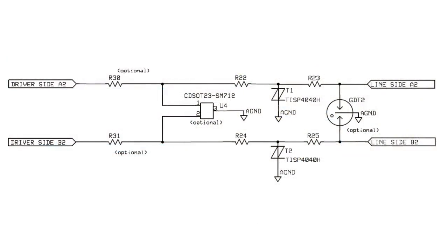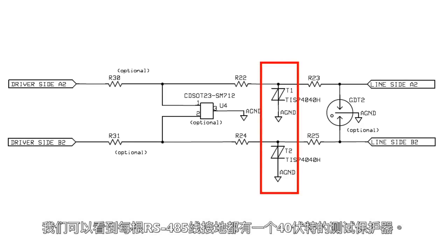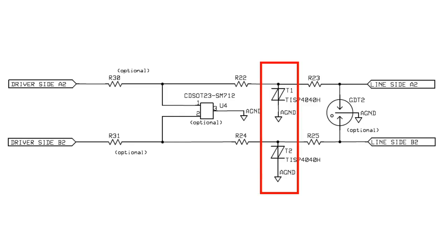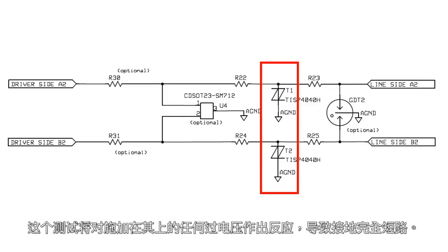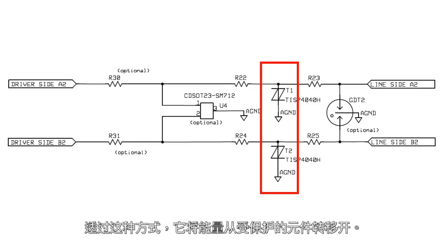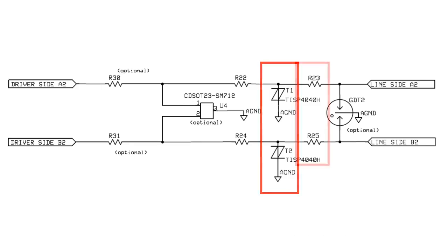Before we go any further, we're going to take a closer look at the protection circuits. This is the circuit diagram for the TISP-based protection. We can see there is a 40 volt TISP protector on each of the RS-485 wires to ground. The TISP will react to any overvoltage applied to it, causing a dead short to the ground. By this means, it will divert the energy away from the protected component.